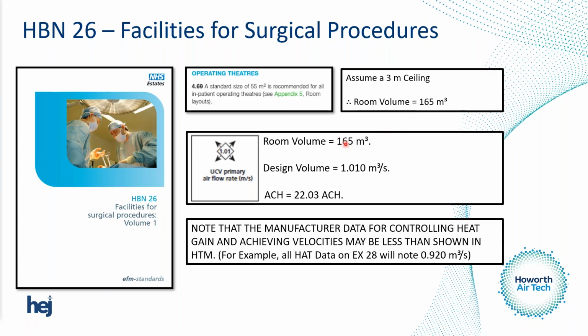If we have 55 metres squared and a 3 metre ceiling, that gives us a room volume of 165. Then we do the calculations that I'm going to show you in a couple of slides, so don't worry about how I've come to this conclusion. We take the room volume and the standard flow rate for a UCV operating theatre from HTM 03 from the standard layouts, do our calculation, and the air change rate works out to exactly what we're after, 22 air changes. The reason it's important to note this is that tomorrow you might order a UCV canopy from a UCV manufacturer, and they'll give you a minimum supply flow rate to the UCV from the HVAC system.